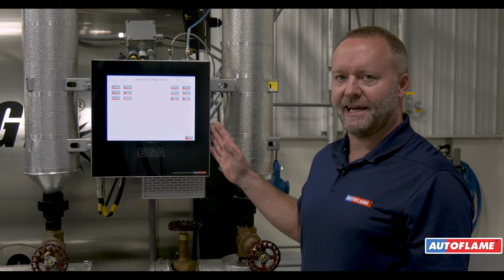Okay, what we've got here is the Autoflame exhaust gas analyzer. This analyzer can be used in conjunction with the Mark 8 controller, so we can use all this information of exhaust gases to trim the burner, or we can use it as a safety device.